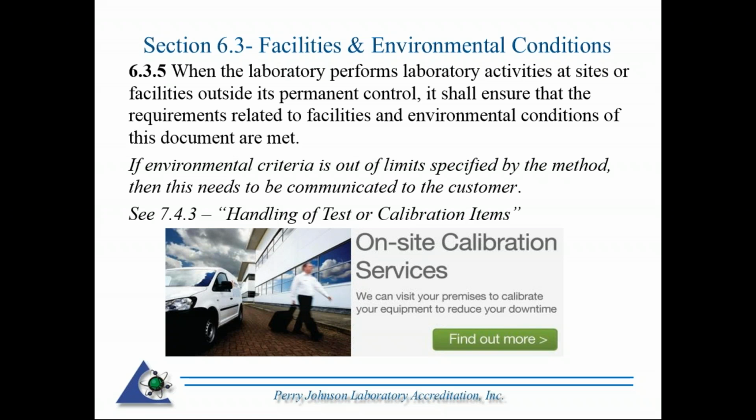So basically, if you're doing work at the customer's location or perhaps in a mobile facility and conditions are out of specifications, the first thing that needs to be done is to bring it to the attention of the customer, the results of that consultation need to be recorded, and then lastly, it needs to be documented on the test or calibration report, including a disclaimer in the report on which results may have been affected by the deviation.